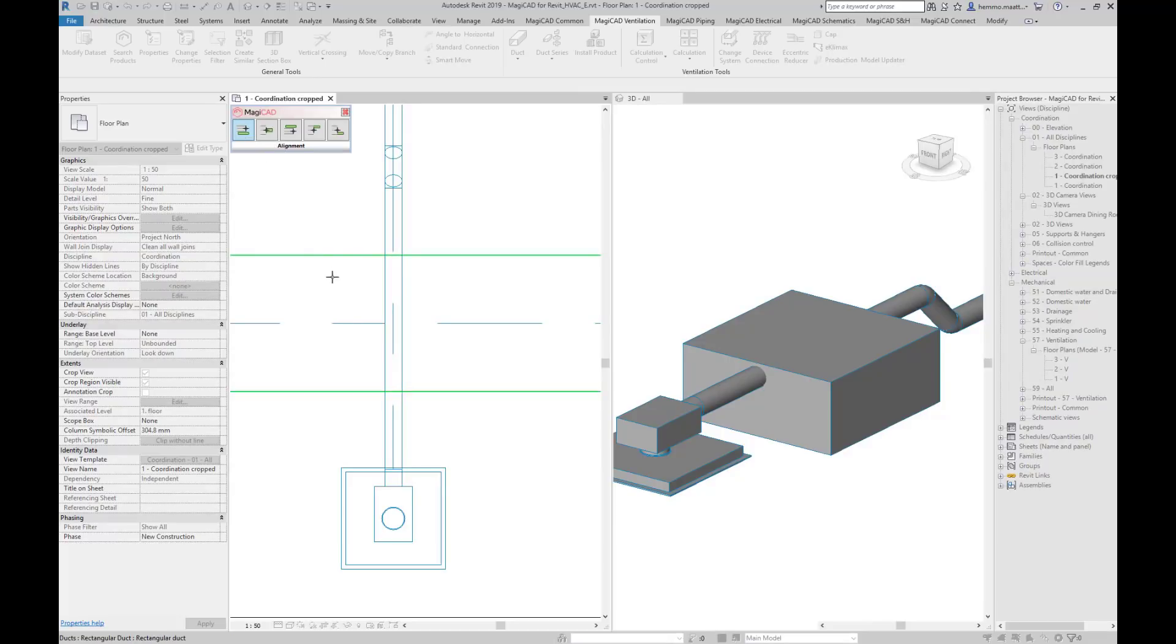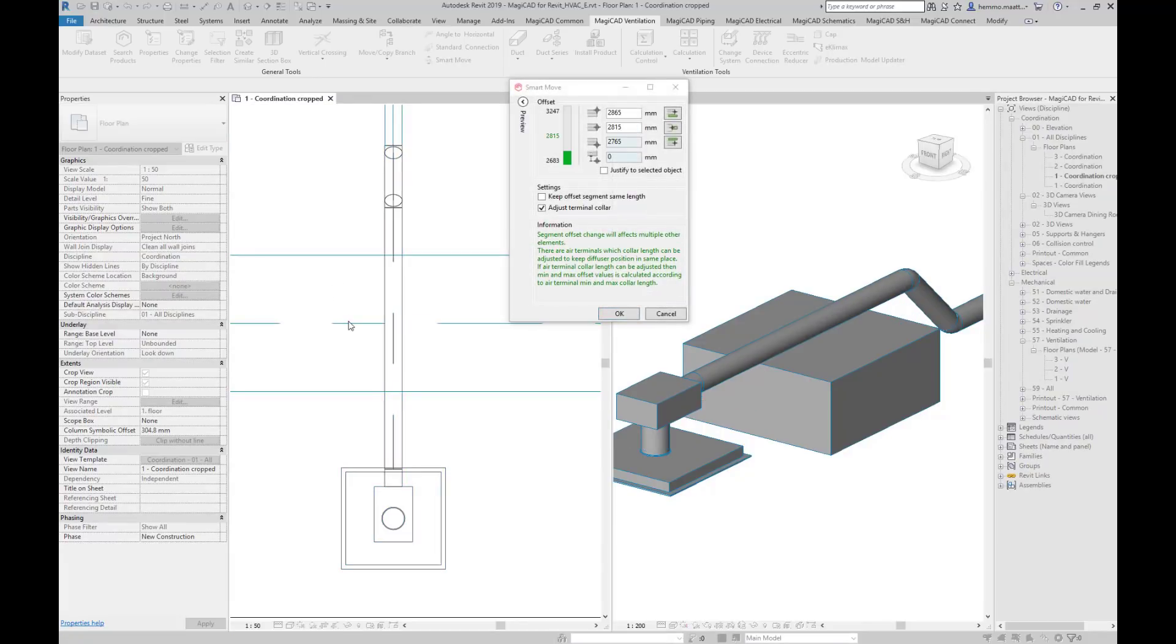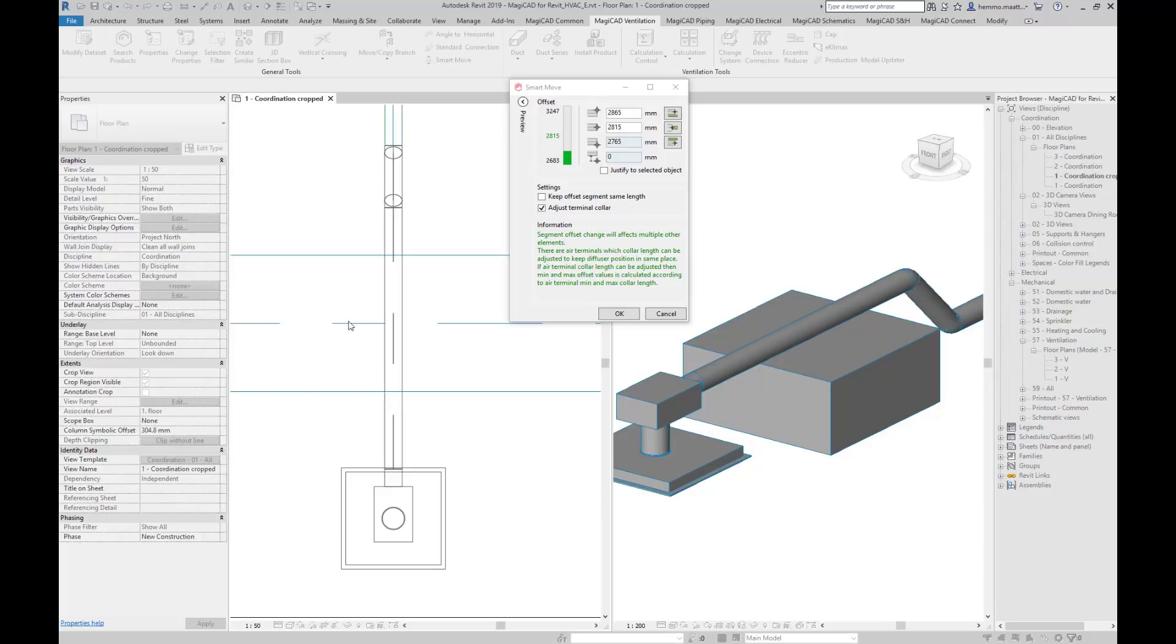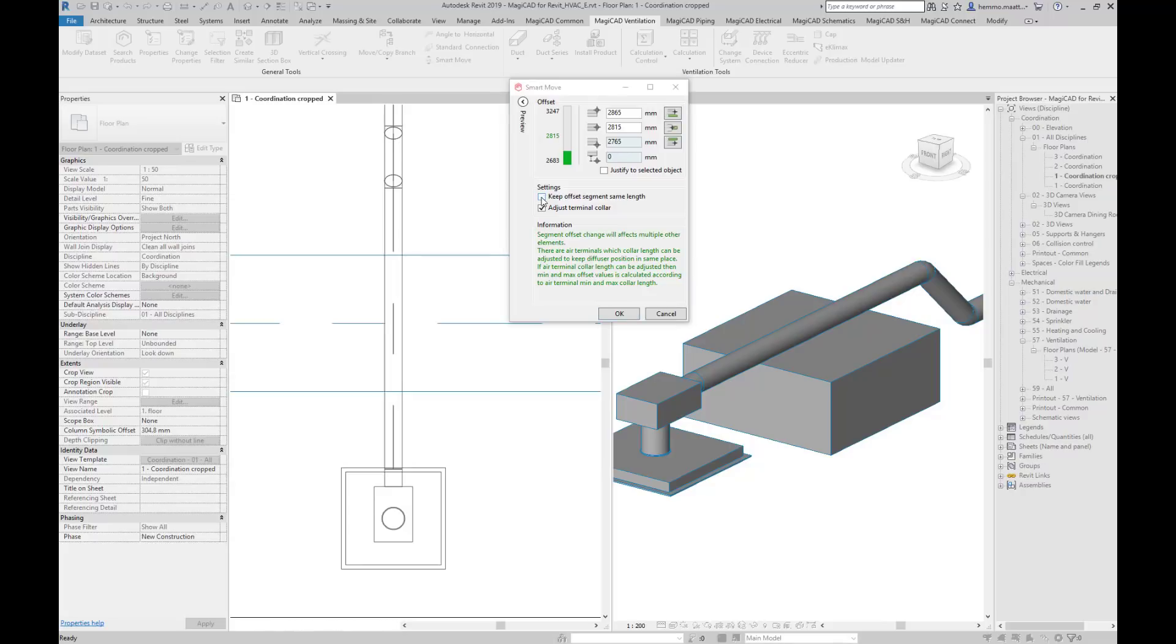Let's take a further look at the options we have in the SmartMove dialog. This time we have a circular duct with 45 degree bends colliding with the rectangular one. Elevating the horizontal round duct segment makes it shorter since we don't want to lose the connection to the angled segment. With the option Keep Offset Segment Same Length we push the angled segment back a little to maintain the old length for the horizontal segment.